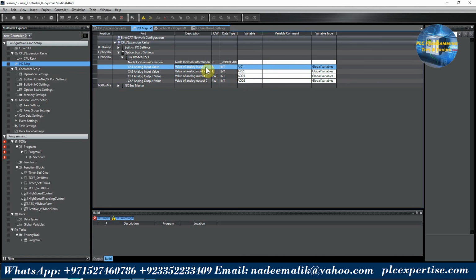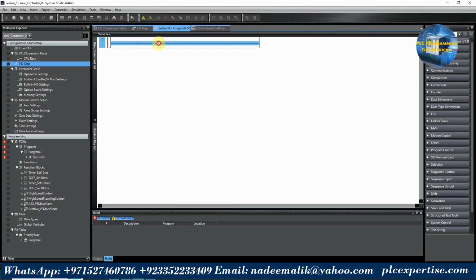Analog input channel 1, we can read the raw value at the AI01 variable. At channel number 1, we have connected a 0 to 10 bar pressure sensor, and its output is 0 to 10 volts. At 0 volts, we will get 0 raw value, and at 10 volts output, we will get 4000 raw value. Now, to change this raw value to some usable engineering units, we have to make some program here.